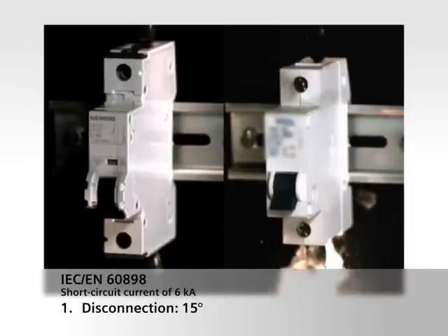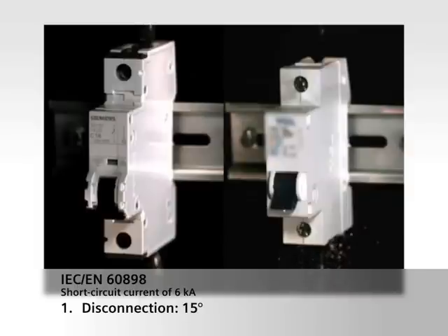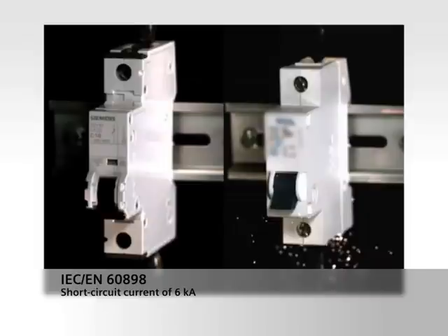The miniature circuit breaker from Siemens trips quickly and safely. However, the device from the other manufacturer requires far longer. This produces both a higher current pulse and enormous internal pressure in the device. The result? Sparks and material fly from the enclosure.